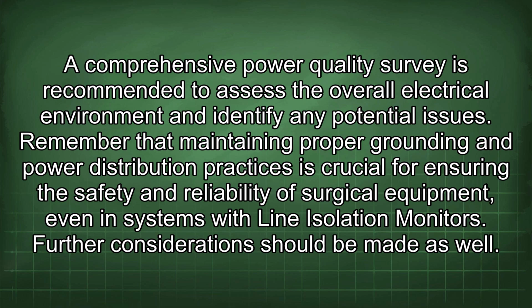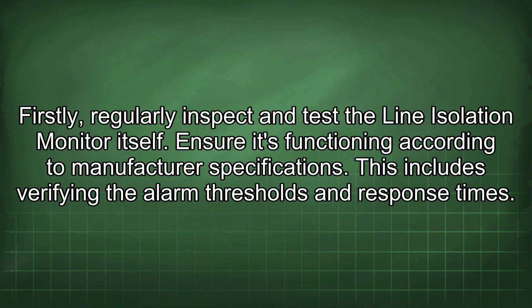Remember that maintaining proper grounding and power distribution practices is crucial for ensuring the safety and reliability of surgical equipment, even in systems with line isolation monitors. Further consideration should be made as well. Firstly, regularly inspect and test the line isolation monitor itself. Ensure it's functioning according to manufacturer specifications. This includes verifying the alarm thresholds and response times.